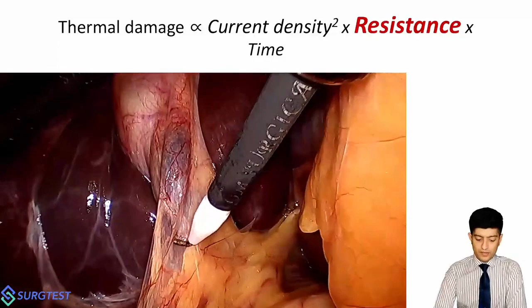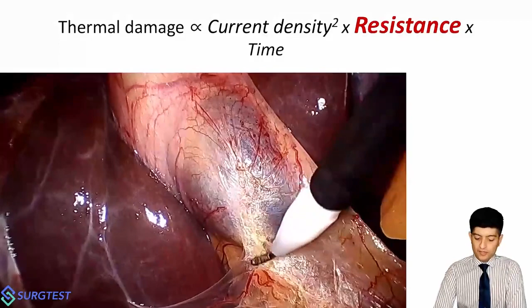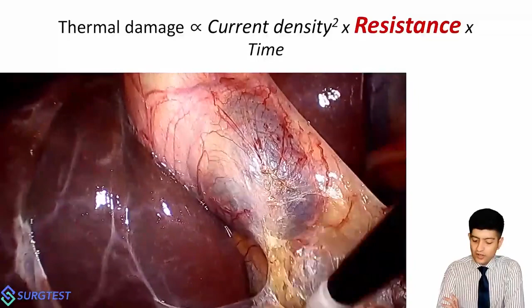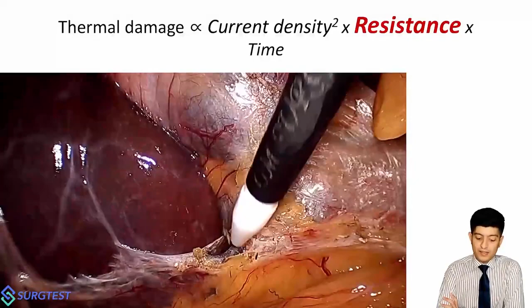This is a video of a lap cholecystectomy with just a few adhesions. You can see all of these adhesions are going to be taken down with the tissues kept at a significant amount of stretch, and a lot of this division is happening only with a continuous low waveform current, which is the reason why you're not seeing any eschar formed within the tissues. You may see tissues getting denatured and whitened out, but you're not seeing any charring or carbonization anywhere. At every given point in time, the tissues are being placed under stretch so that the energy delivery is efficient and tissues get divided extremely well.